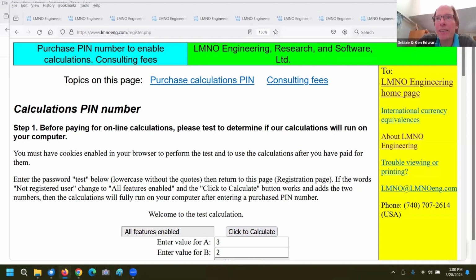When I run EPANET, it will give me a pressure at each node, and I for sure will run our little bitty calculation for a single pipe to verify that EPANET gave me the proper pressure loss between those two nodes for that diameter, length, minor losses, whatever. So I will always make sure, because maybe I selected by accident defaults for EPANET that were SI, and I wanted to use English units, something dumb and fundamental like that.